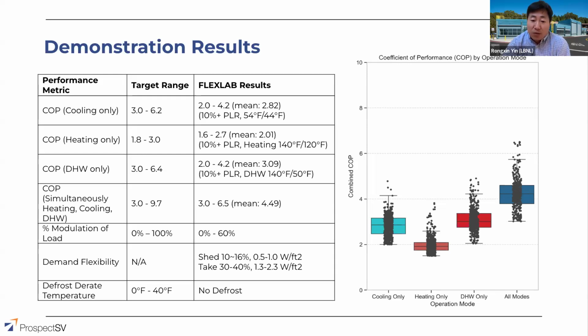And the COP ranges between 2 and 4.2, and the mean COP for domestic hot water only is roughly 3.1. Regarding the combination mode, as mentioned on the first slide, when the unit is providing chilled water, hot water, or even domestic hot water at the same time, the combination mode COP is pretty nice because we recover all the heat released from the cooling cycles. The COP ranges between 3.0 and 6.5, and the mean COP is up to 4.5. This is the overall COP performance of the unit in individual mode and in the combination mode that runs cooling and heating simultaneously.